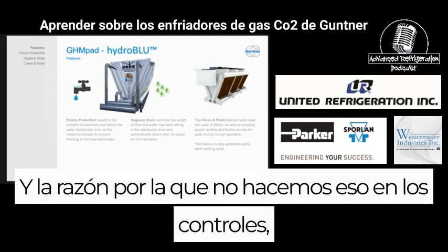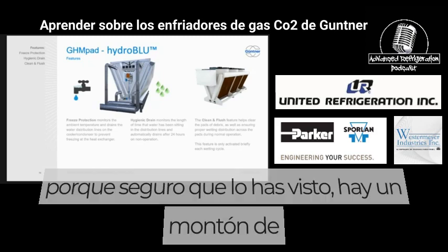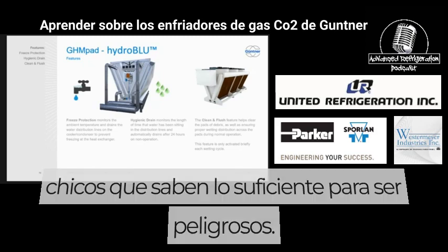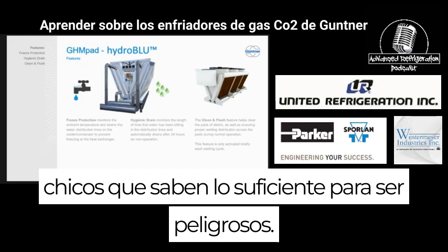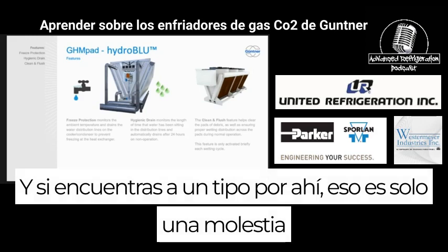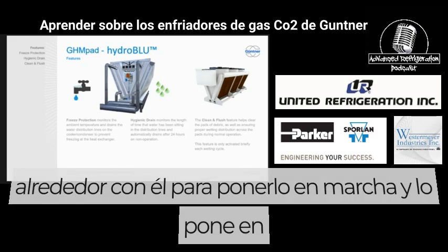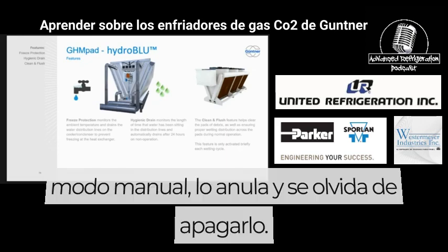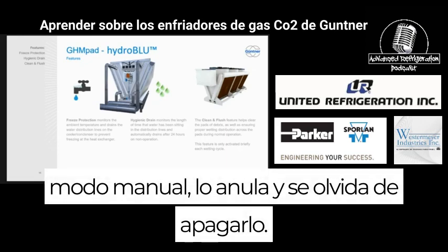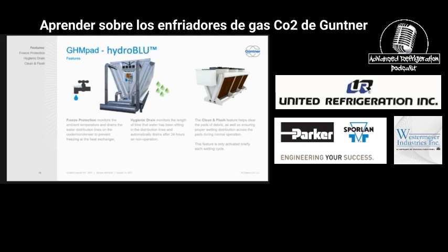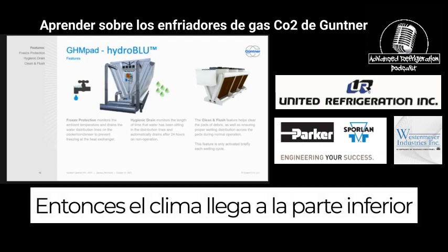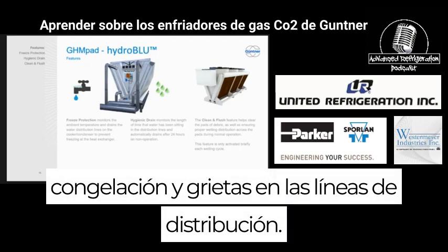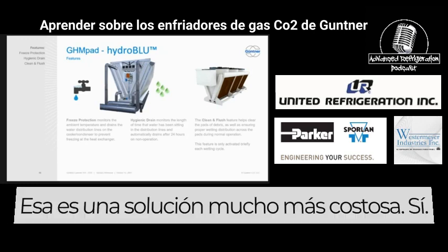No, and the reason we don't do that in the controls, because I'm sure you've seen it, is there's a lot of guys that know just enough to be dangerous. If you get a guy out there that's just messing around with it for starting it up and puts it in manual mode and overrides it and forgets to turn it off, then it freezes. The weather gets below freezing and cracks the distribution lines. That's a much more expensive fix.